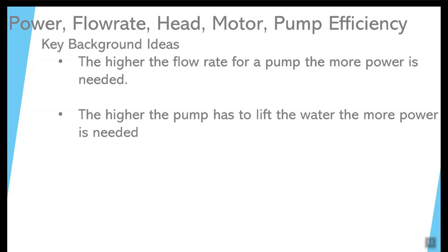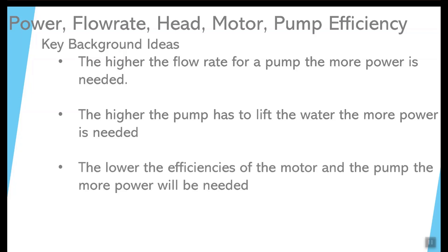The second variable is the higher that you have to lift the water against gravity, the harder the pump is going to have to work and therefore more power will be needed in kilowatts. The third concept is that just because you have power coming into the system doesn't mean all of it will translate into lifting water. There is efficiency loss in the motor and the pump that will cause the output to be lessened, so you're going to have to increase your input of power in kilowatts.